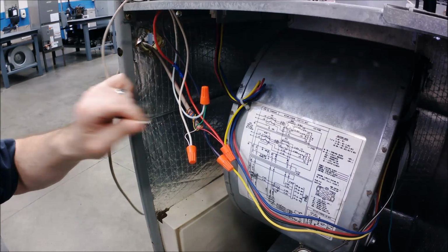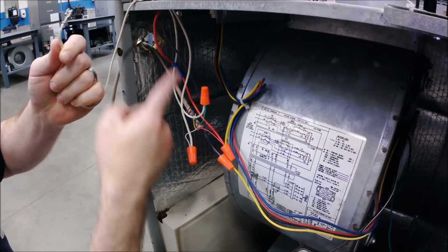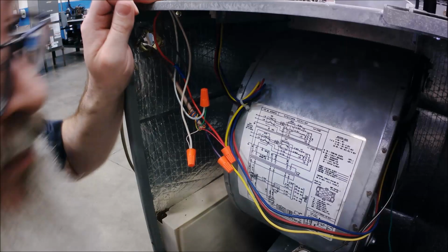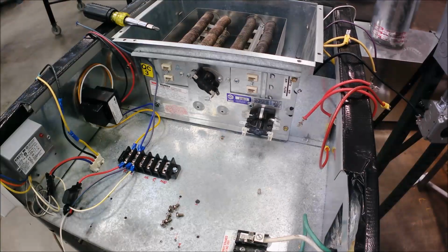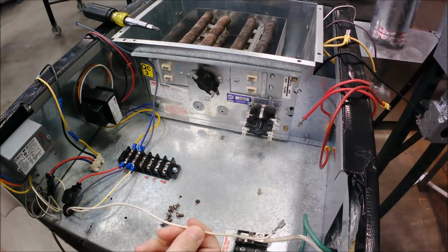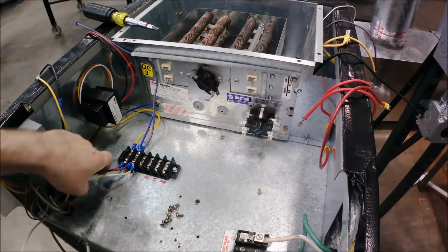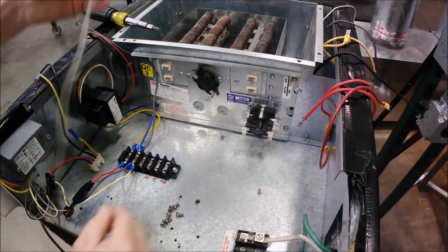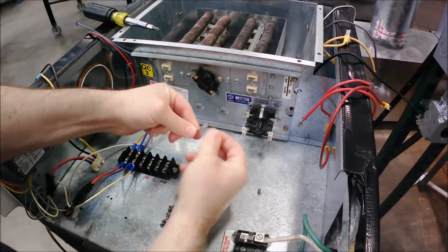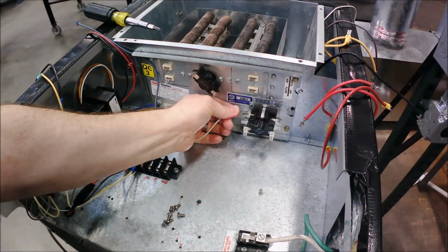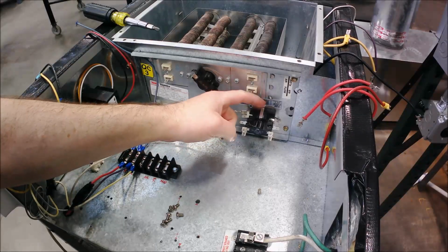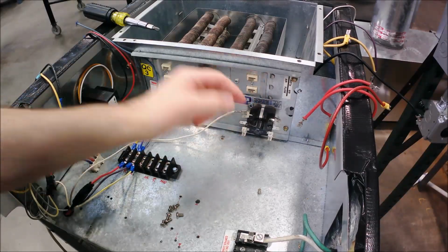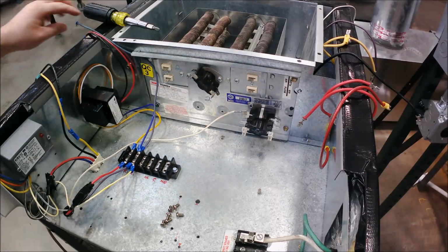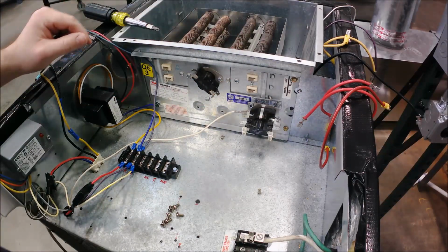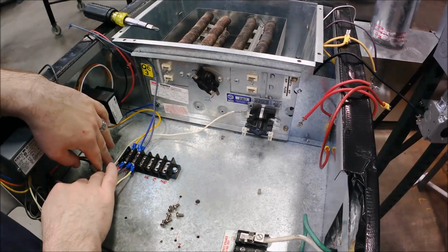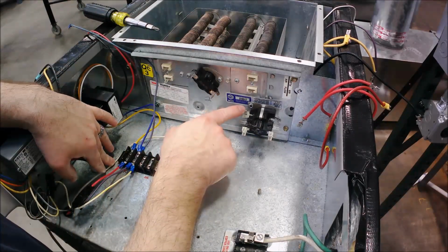But we've got electric strips here, so once this white leaves this wire nut, we're going to wire it to our sequencer. Our white right here, we can try to make this as neat as possible. We'll just loop it under here, on this bottom connection, usually the one closest to that plate. I would say the bottom, but this thing's mounted on its side, so somebody somewhere is going to get me. But the W from the thermostat is ultimately going to go to that heat sequencer.